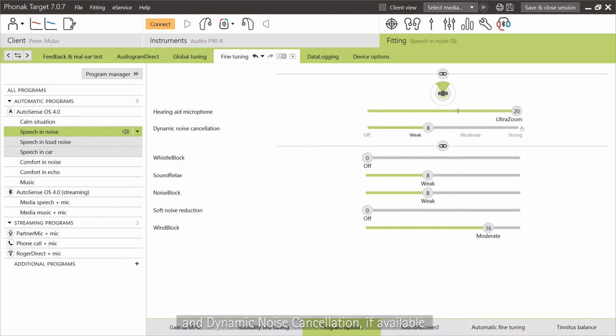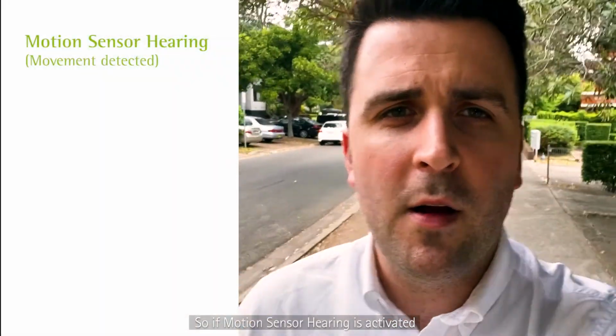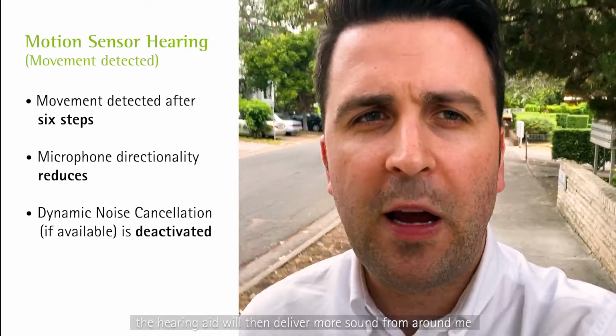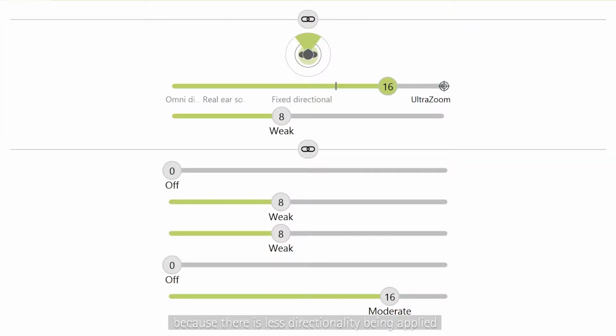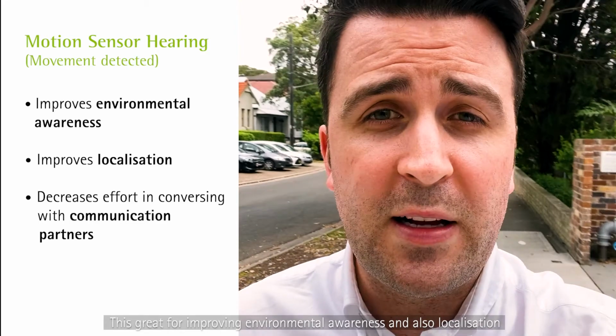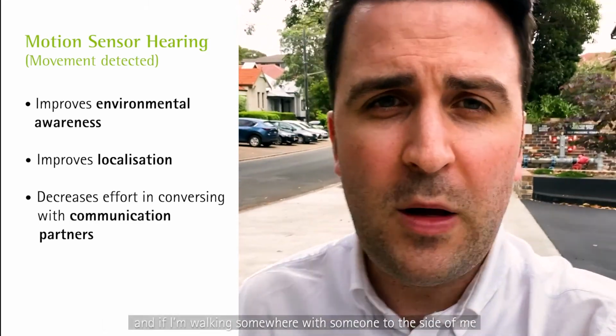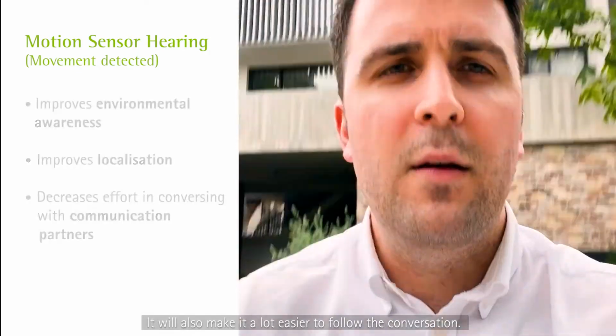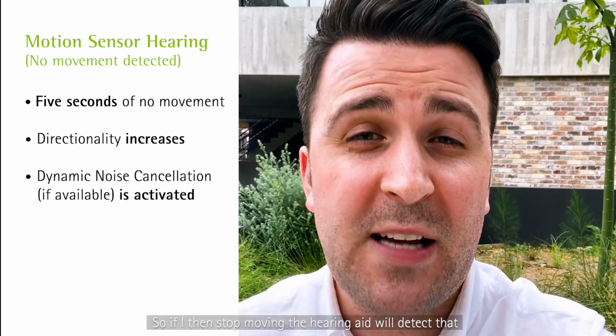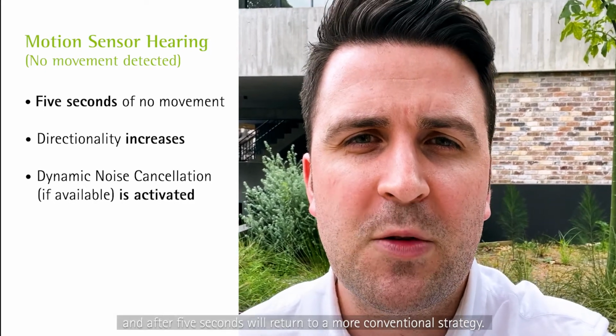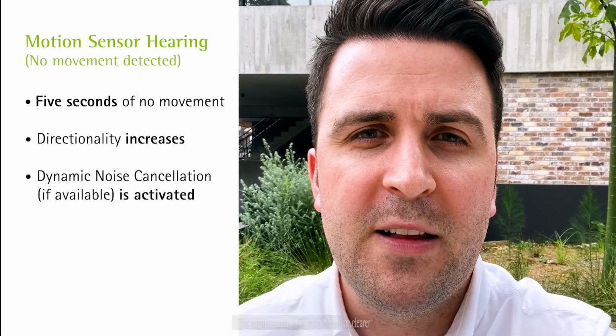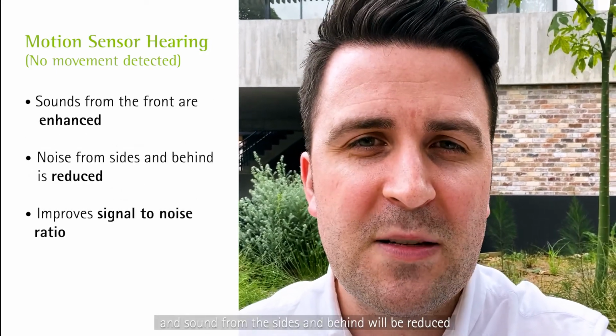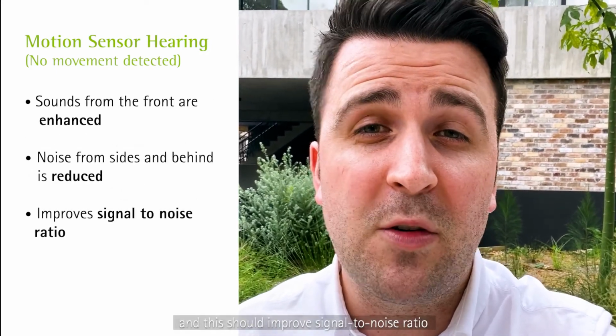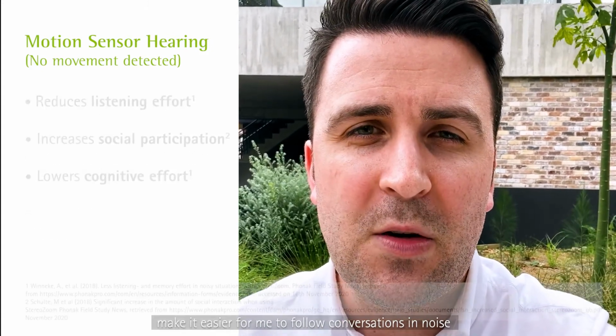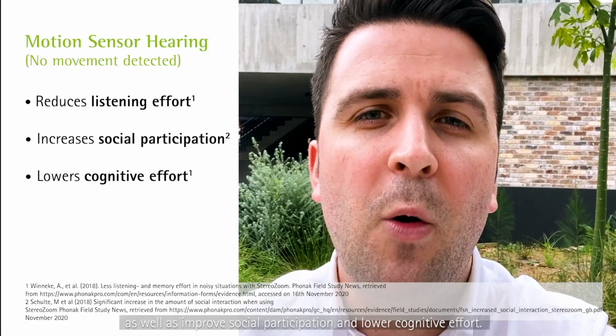So if motion sensor hearing is activated, when I'm in movement and I've taken more than 6 steps, the hearing aid will then deliver more sound from around me because there's less directionality being applied. This is great for improving environmental awareness and also localization. And if I'm walking somewhere with someone to the side of me, it'll also make it a lot easier to follow the conversation. So if I then stop moving, the hearing aid will detect that, and after 5 seconds, return to a more conventional strategy using directional microphone modes. This means sound in front of me will be clearer and sound from the sides and behind will be reduced. And this should improve signal to noise ratio, make it easier for me to follow conversations in noise, as well as improve social participation and lower cognitive effort.